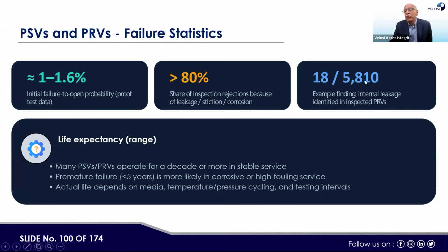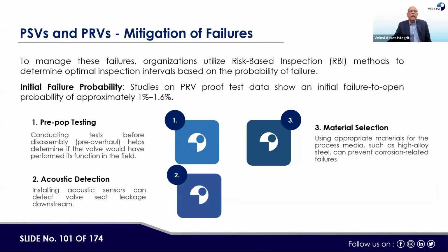Then 18 PSVs out of 5,810 is an example, finding internal leakage in the inspected PRVs. These PSVs were found internally leaking. So normal life expectancy is 5 to 25 years that they can work. Then, initial failure probability: studies on PRV proof test data show an initial failure to open probability of approximately 1 to 1.6%, and this is from pre-pop testing. Then there is acoustic detection and material selection. These aspects may minimize these problems. Like we do pre-pop testing at proper intervals, or installing acoustic sensors can detect valve seat leakage. If the valve is leaking, then appropriate material of construction is a job for the engineer at the project stage.